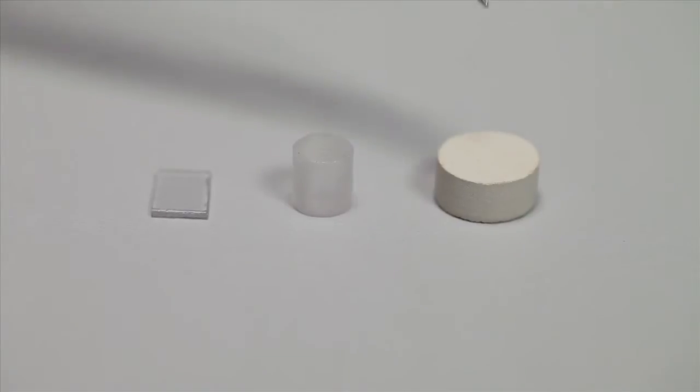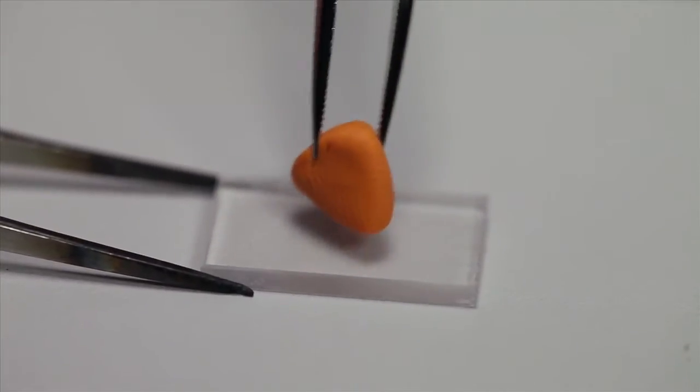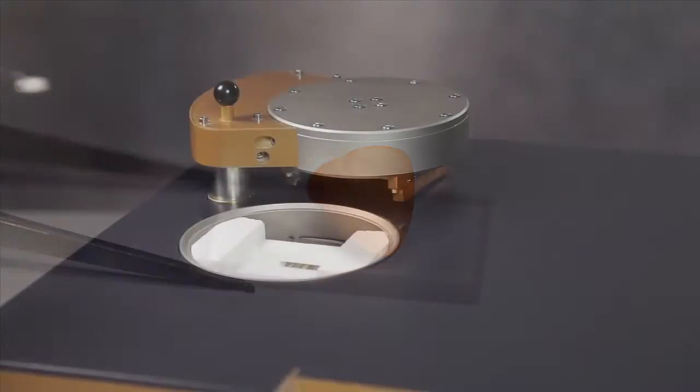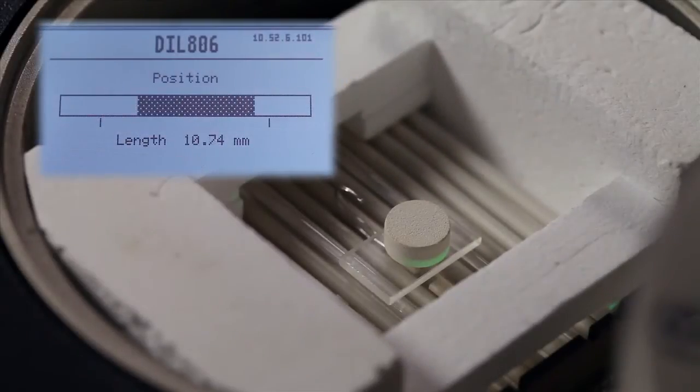Samples could be optically opaque, translucent, or transparent. Samples could be measured in different directions, facilitating identification of anisotropic thermal expansion. You simply place the sample on the sample holder and the measuring system will detect its size.